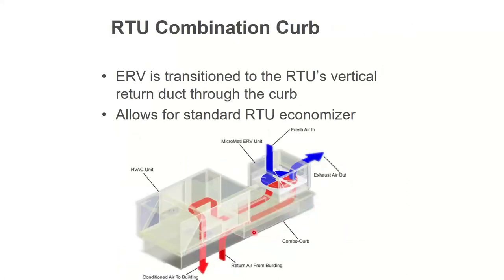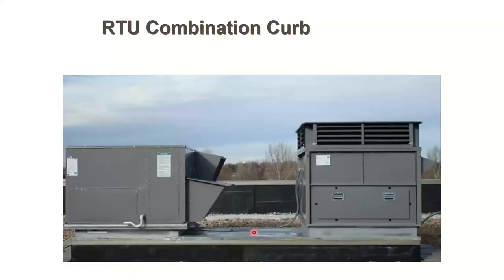So you've got one curb where a rooftop and ERV both sit on top of it and the ducting is in between them, inside the curb. That's another way to do it. It's kind of ugly, but it's on a roof, so who cares? Here's your standard rooftop. Here's your combo curb. Here's your ERV. Fresh air on this guy gets sucked in, goes through one side of the ERV or through the curb and goes into the unit as if it was the return.